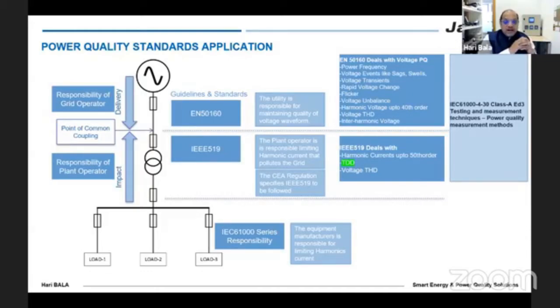And then IEEE 519 comes and says, look, consumers create current harmonics. Because of current harmonics, the voltage can get distorted. So it is a shared responsibility of the utility and the consumer to maintain the power quality in terms of IEEE 519, which means harmonic current is the responsibility of the consumer and the voltage is the responsibility of the utility. So it means it's a shared responsibility between the utility and the consumer.